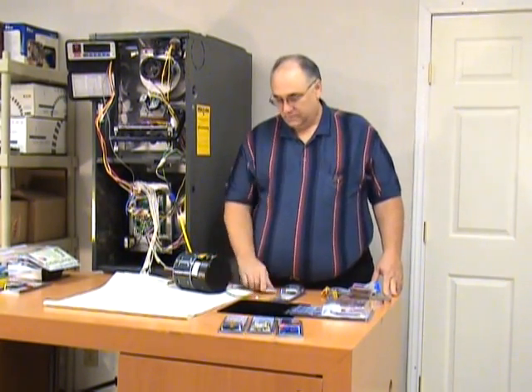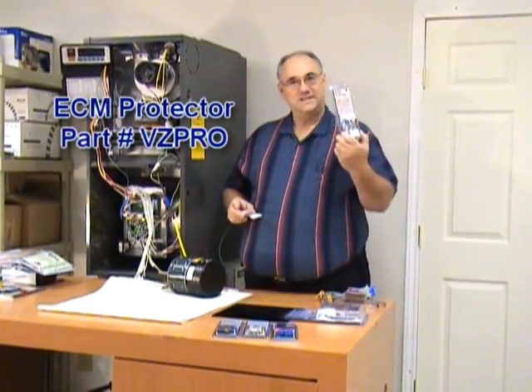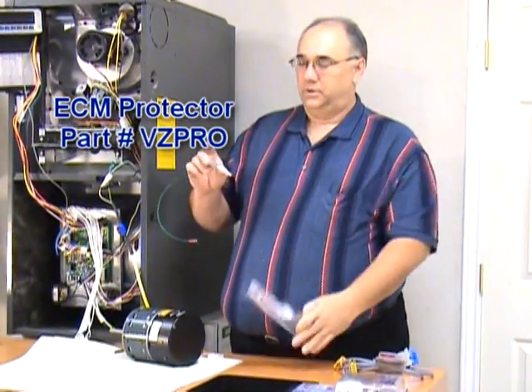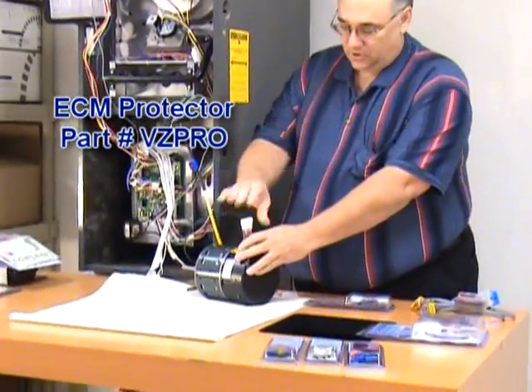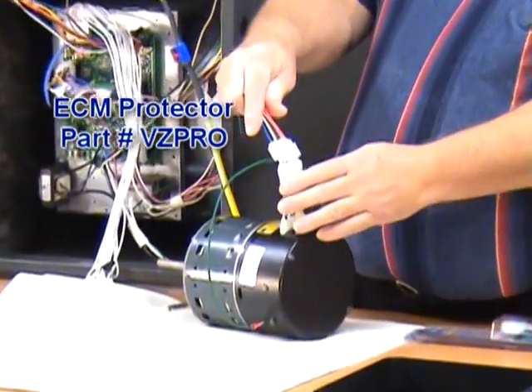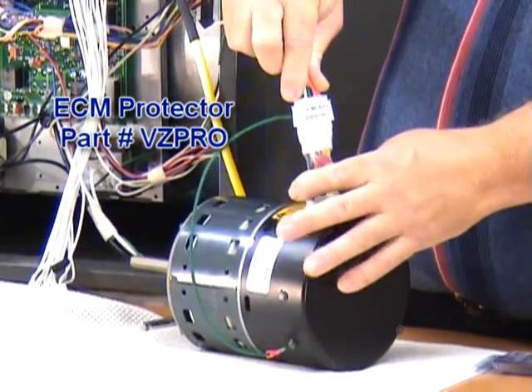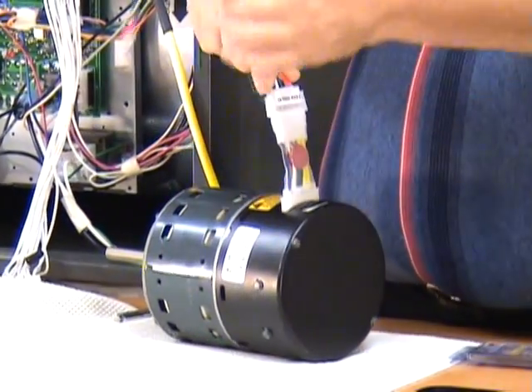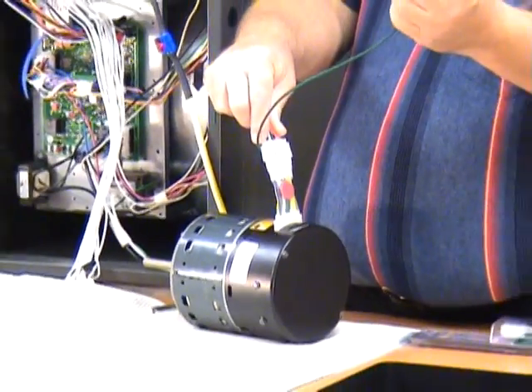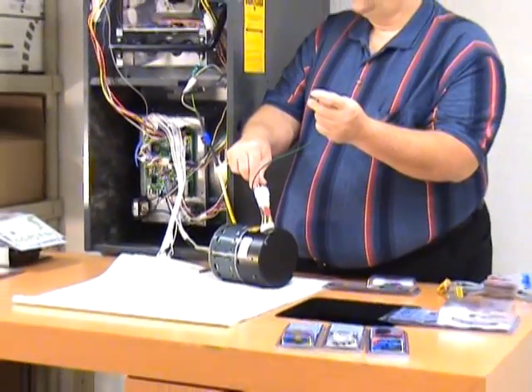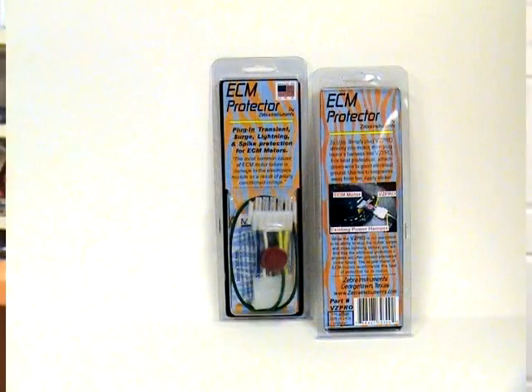The next biggest cause of failure for an ECM motor is surges and spikes wrecking the electronics in the end housing. To that end, we've come up with a product called the ECM Protector. It's a plug-in device that plugs into the motor before your normal power cord plugs in. Sits there in line with it. It's terribly easy to install. If you want a little bit of added protection, you hook up this second ground strap to a good metal connection inside your furnace. It's a fast add-on sale to help your customer protect their equipment.